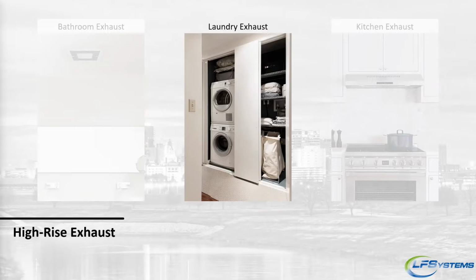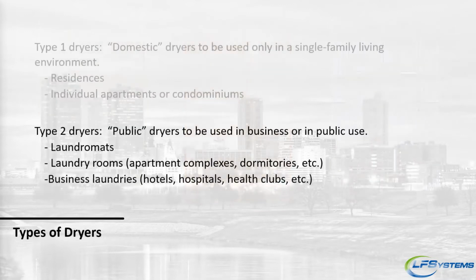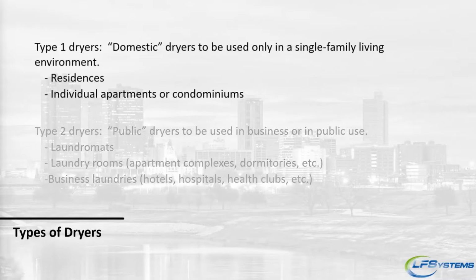both bathroom and kitchen. And to understand the difference between the dryers, type 2 dryers are, again, those public dryers more for commercial laundromats, laundry rooms. They can be in high-rise exhaust systems where you're having a laundry room on each floor. They do have slightly different requirements as far as exhaust pressures and length of run. What we're going to focus on is the type 1 dryer. These are domestic individual dryers in the space themselves.